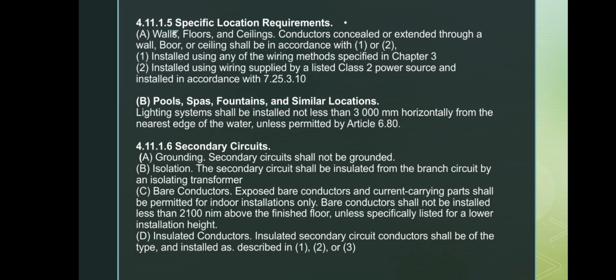This is the specified location requirements. Now, for installation rules. Conductors that pass through walls, floors, or ceilings must follow the wiring methods in Chapter 3 or be supplied by a listed Class 2 source. When installations are near pools, spas, or fountains, lighting must be placed at least 3 meters from the water unless allowed by Article 680.